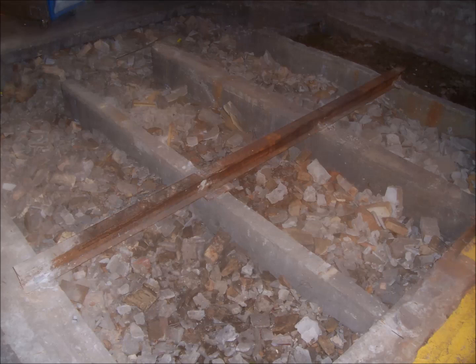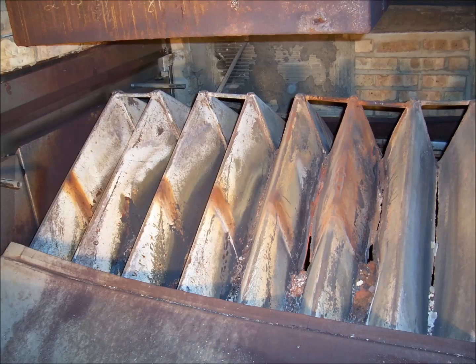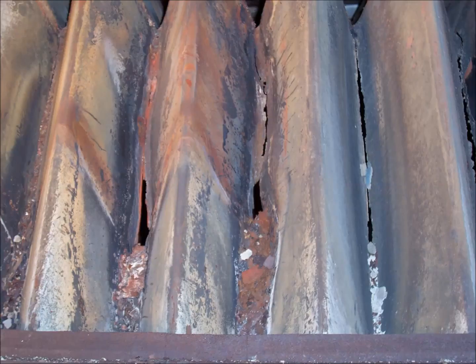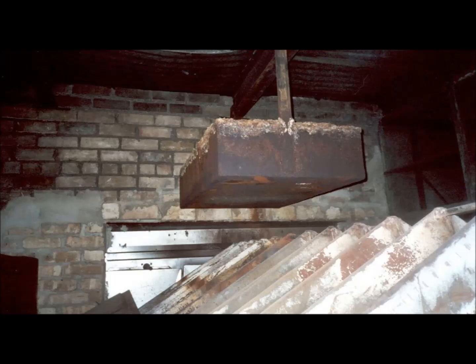Below the brick enclosure are 4 concrete chambers where air flows up over the heat exchanger. These chambers extend down 6 to 7 feet, but when this photo was taken, they had been filled in with old bricks ready for paving over. This is the top of the heat exchanger which has the combustion chamber inside of it. You can see how it has rusted out. This is the humidifier water tray located above the heat exchanger.